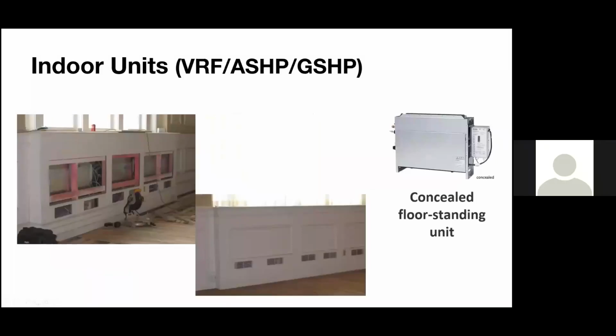Then we go to our concealed floor standing units. I forgot to mention, but the returns are down at the bottom, and then you have your supply coming up the top. I call these the church models. The reason for that is we don't really like to touch what's already been built in the church. However, a lot of the time you want to replace your heating source that's way over its lifetime. So what you're able to do is rip those out and add in these concealed units, basically take a little window out, and then you can go back, do the same millwork, and it almost looks like you haven't even touched it. It looks the same. However, you are now getting cooling and heating out of this unit.